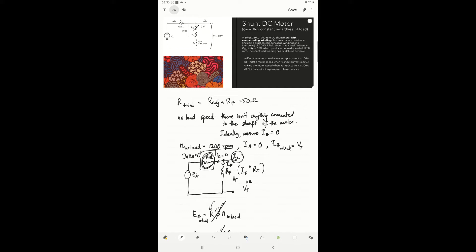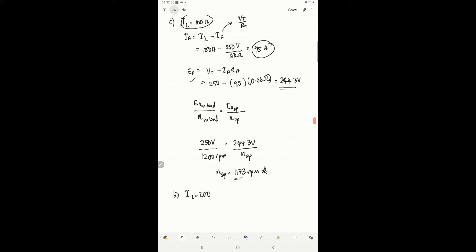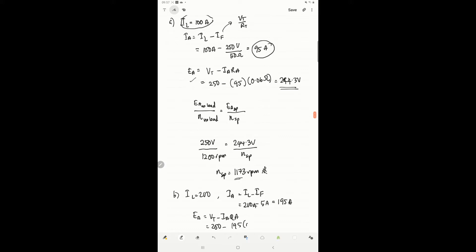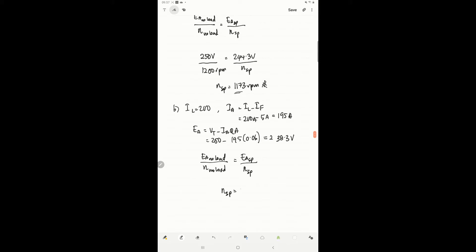As the torque produced needs to increase, the input current increases as well. So what happens when we increase to 200A? If IL equals 200, we know that ia equals IL minus IF. So it's 200 minus 5 ampere, giving ia equals 195 ampere. Then ea equals VT minus ia·Ra, which is 250 minus 195 times 0.06, giving 238.3 volts. Using the ratio of ea at no-load over speed at no-load, we get a speed of 1144 rpm.